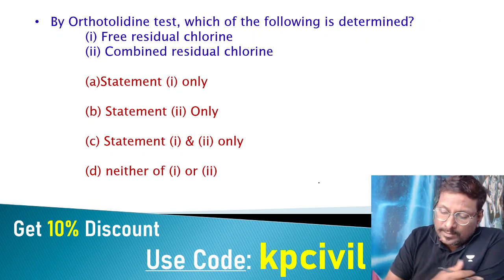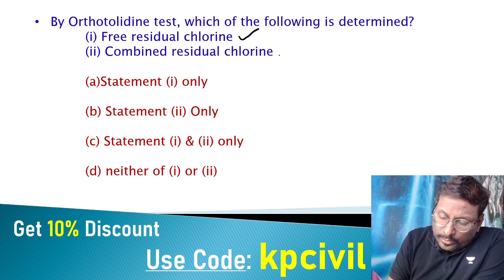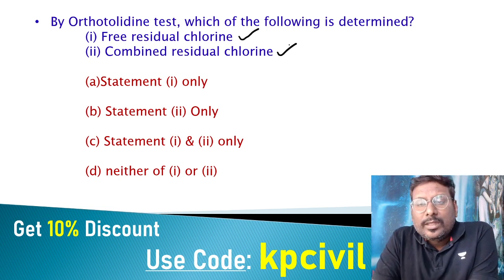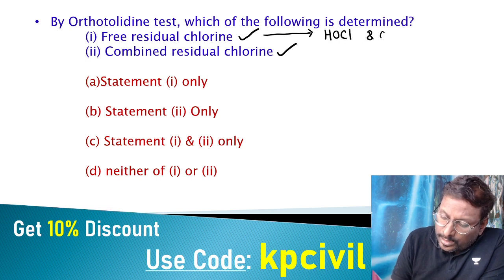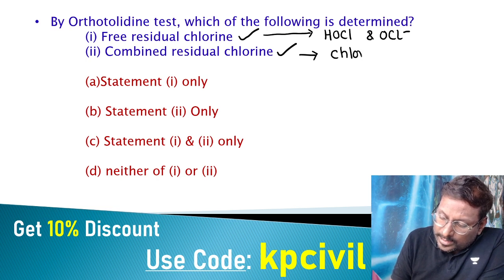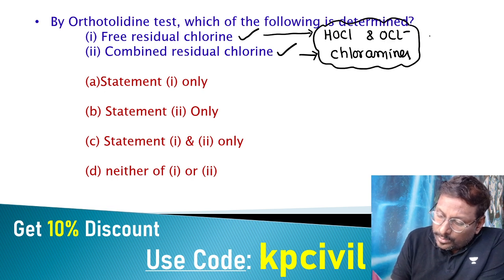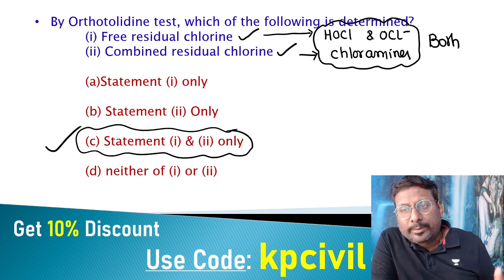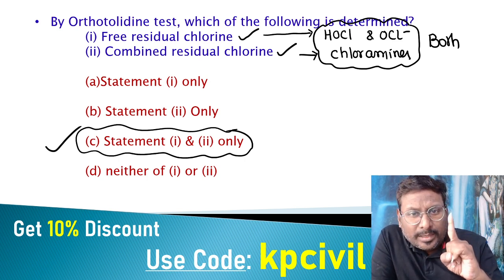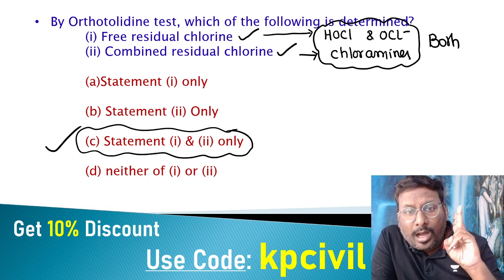The orthotolidine test is used to find out both free residual chlorine and combined residual chlorine. Free residual chlorine includes HOCl and OCl⁻. Combined residual chlorine is chloramines. Orthotolidine test finds both. Residual chlorine — whether free or combined — can be estimated by the starch-iodide test or the orthotolidine test.